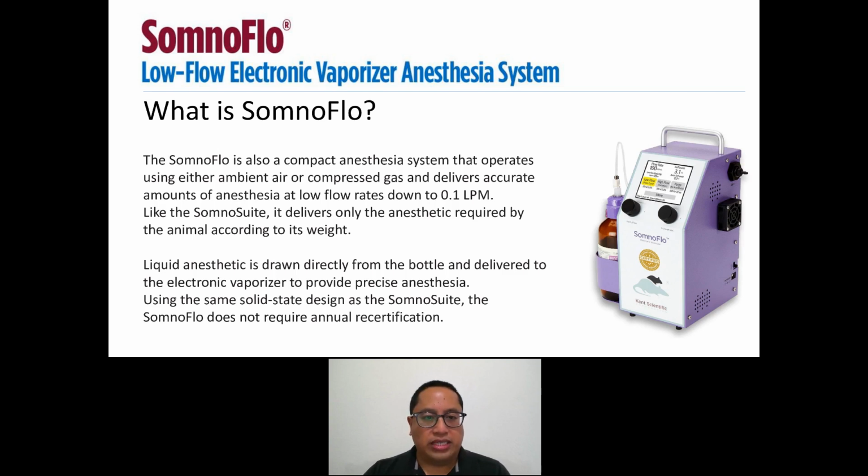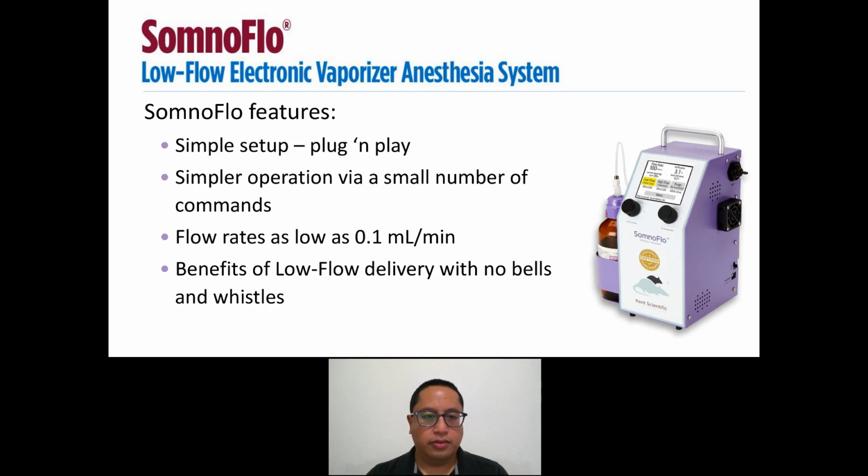Unlike the SomnoSuite, the SomnoFlo sources the anesthesia directly from the bottle and primes automatically, allowing you to start your procedures soon after powering on the system. Like the SomnoSuite, the SomnoFlo gives you the choice to use either ambient air or compressed gas as your carrier for the anesthesia.